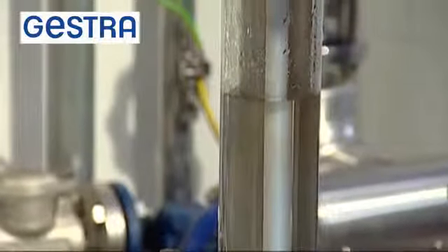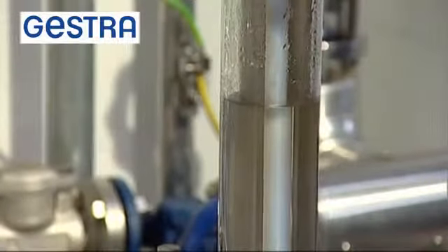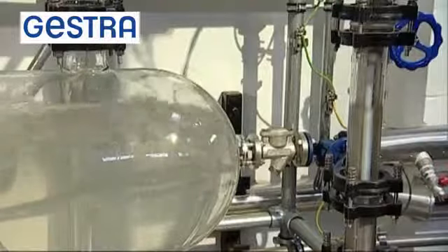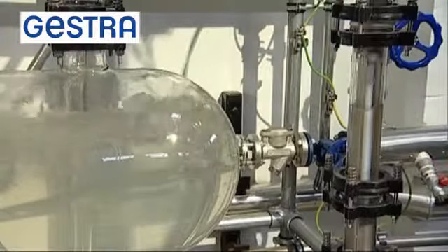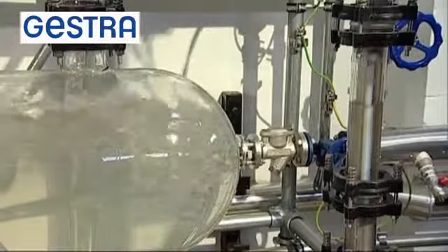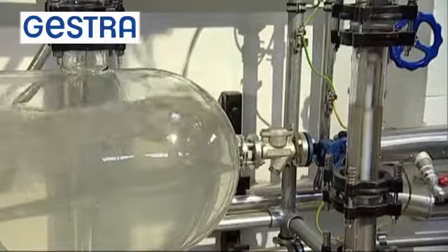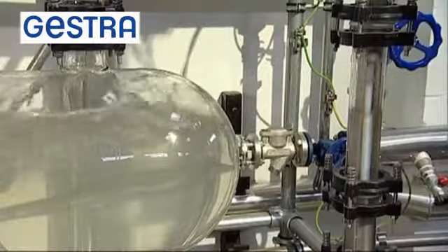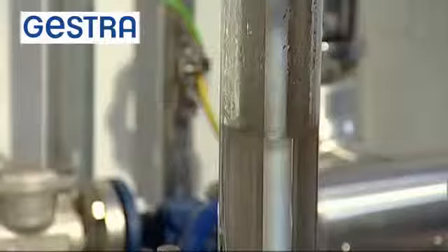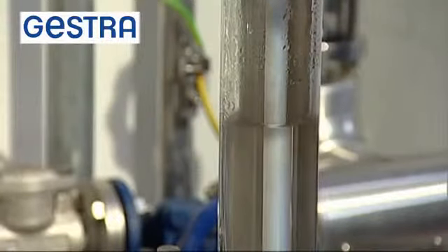Through the sinking pressure, the area loading on the individual steam bubbles in the water is reduced, so that these occupy a greater volume, lifting the water level as a result. This effect can also be observed in the external measuring pot. Indication errors cannot be excluded.